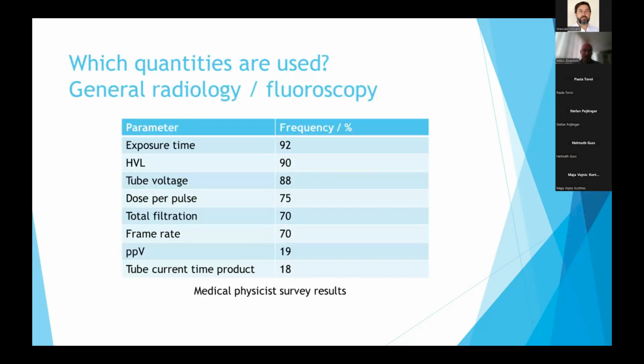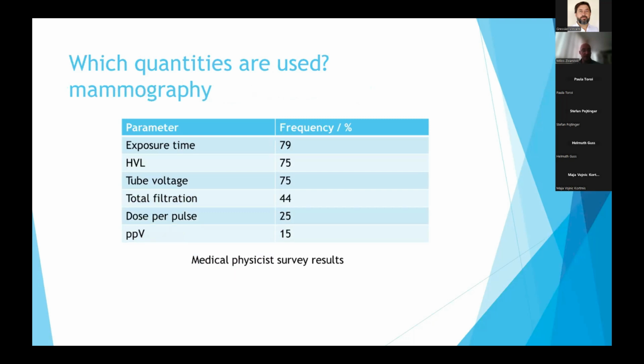So just shortly in the beginning, we were interested if all of these quantities are actually used in clinical practice, if they're necessary. Because if something is not used, you do not need to put effort into standardizing it and providing traceability. I was a little bit surprised to see that almost all of these quantities listed in this table are used by the majority of medical physicists in general radiology. The majority of them use exposure time, HVL, tube voltage, total filtration measurements, etc. And if you look at mammography applications, again, there are multiple quantities besides air kerma that are commonly used and that therefore need standardization and traceability and all the attention that the metrological community can give them.